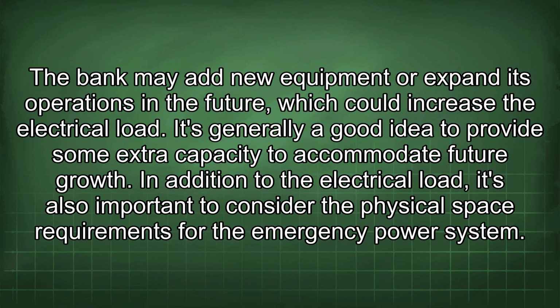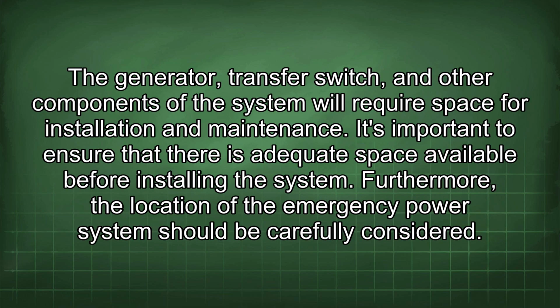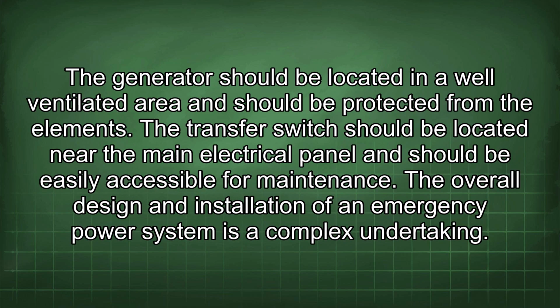In addition to the electrical load, it's also important to consider the physical space requirements for the emergency power system. The generator, transfer switch, and other components of the system will require space for installation and maintenance. It's important to ensure that there is adequate space available before installing the system. Furthermore, the location of the emergency power system should be carefully considered. The generator should be located in a well-ventilated area and should be protected from the elements. The transfer switch should be located near the main electrical panel and should be easily accessible for maintenance.